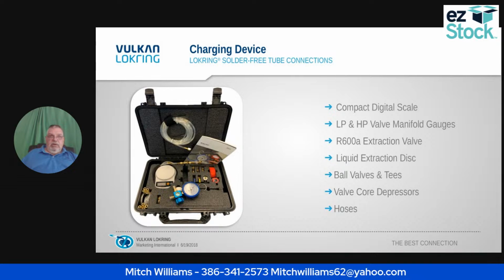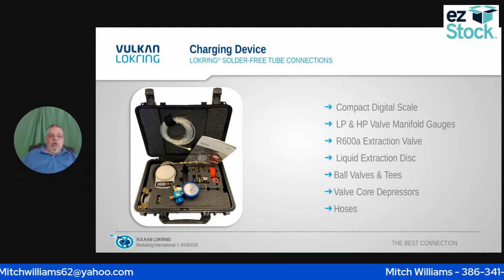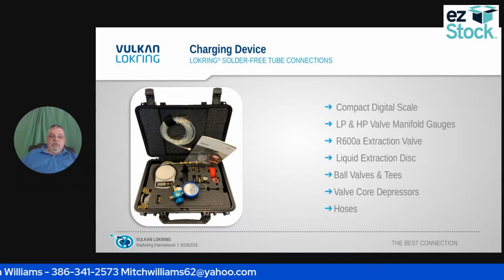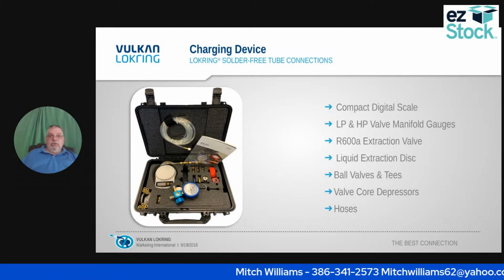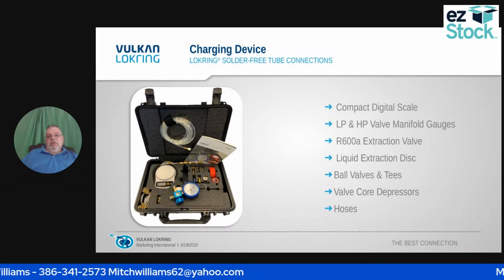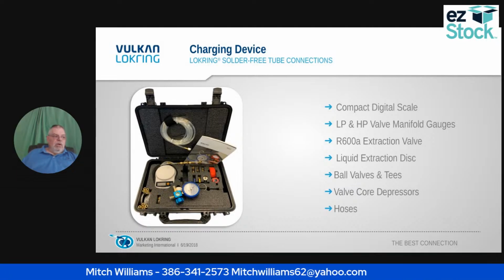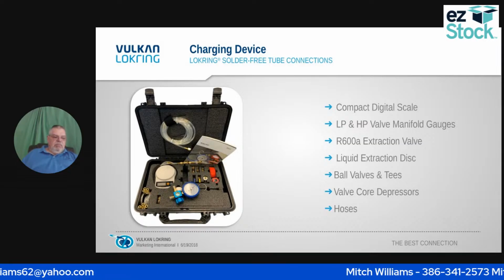Whenever I was doing refrigerators in my prime, I had a bag because I didn't want to haul in all that stuff. So what I would do is I would do maybe 2 or 3 refrigerators in a day. I would drop it into the bag. At the end of the day, I had my recovery equipment at the house. I would go home, pop a cold Coke, and evacuate the bag. Okay, so you just got to be careful. I'm always going to hold and put everything into a bag.